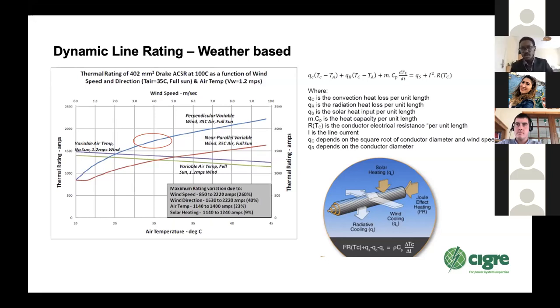However, using weather-based monitors for dynamic line rating offers various advantages, such as it's very cheap and it's very easy to install. However, there are certain disadvantages. For example, even though we would love to optimize the wind speed along the length of the line, determining what the actual wind conditions are along the length of the line is very difficult, because extrapolating the global data over local terrain is harder, because the speed of the wind locally is really a function of the topography of the line. So in order to do that, you really have to perform CFD simulations, and it's more data intensive. So what's usually optimized is the air temperature, but you don't get massive increases by using air temperature.